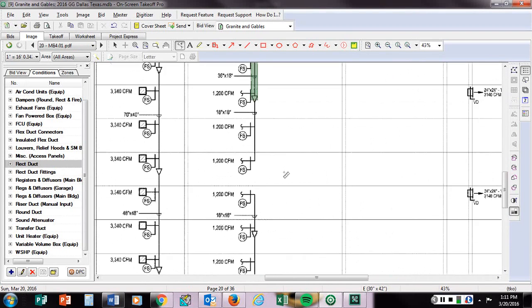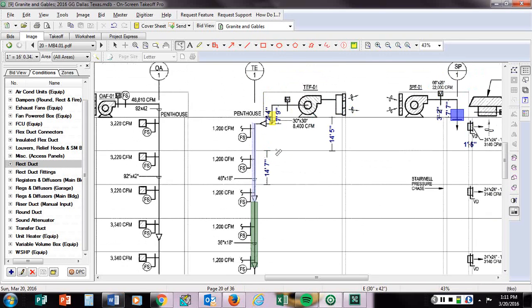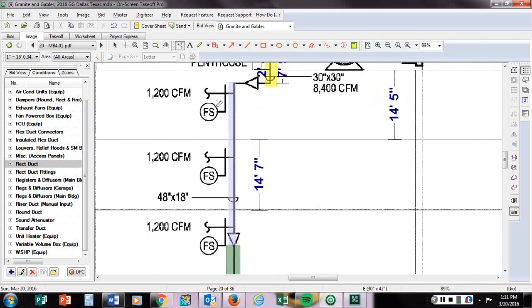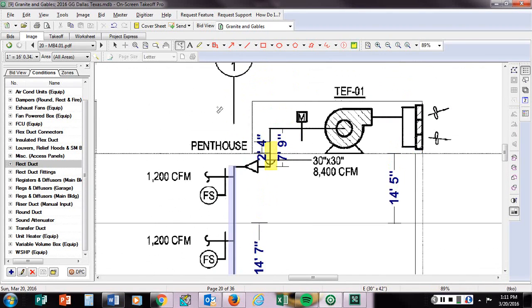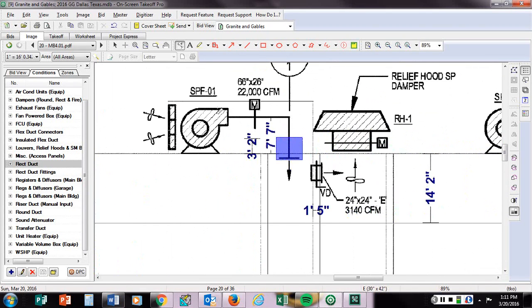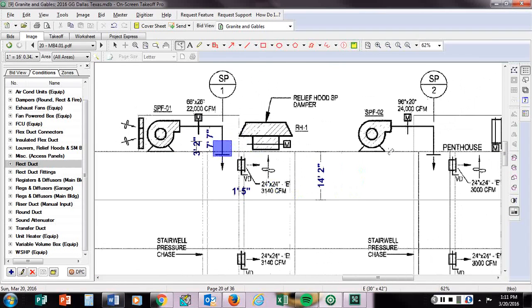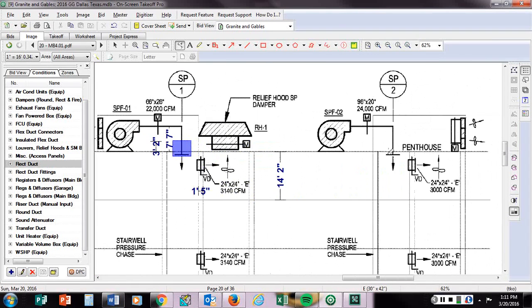So back to our riser diagram, what I'd just ask you to be careful on as you're doing this is that this fire and smoke damper is shown in 2 different locations. Make sure you count it 1 time. As I continue to go to the right, you can see this happens to be the stairwell pressurization fans. There's 2 of them on this building. Their job is really to try to lower the stack effect that's happening with the building by pressurizing the stairwells and not letting them act as a chimney inside of the building, as a conduit for air to go from the lower floor up, or on super hot days from the upper floor down, as the cold air will fall.